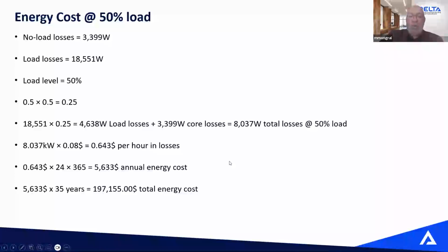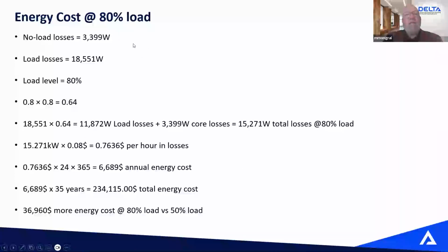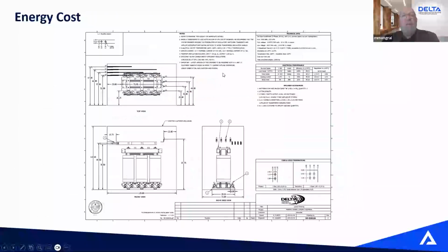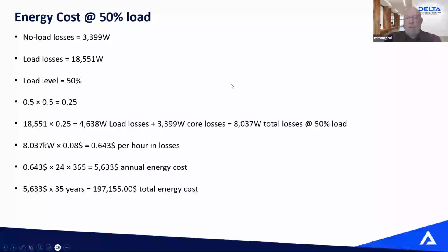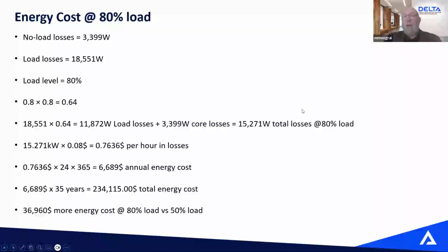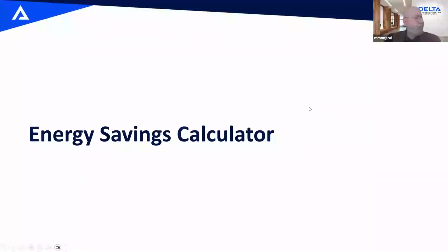Again, if you compare to an old inefficient transformer, you're going to save a lot of money. Same maths at 80% load, you end up at $234,000. So you have almost $37,000 difference over the lifetime of a transformer comparing 50 to 80% load. So again, the more you load, the less you are efficient. But the moral of the story here is if you have an old transformer, it's going to cost you a lot of money. So replacing that transformer will save you a lot of energy, cost of energy.